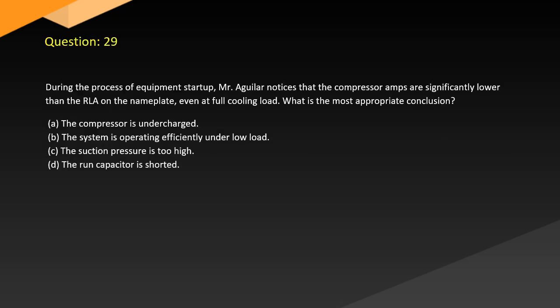Question 29. During the process of equipment startup, Mr. Aguilar notices that the compressor amps are significantly lower than the RLA on the nameplate, even at full cooling load. What is the most appropriate conclusion? A. The compressor is undercharged. B. The system is operating efficiently under low load. C. The suction pressure is too high. D. The run capacitor is shorted.